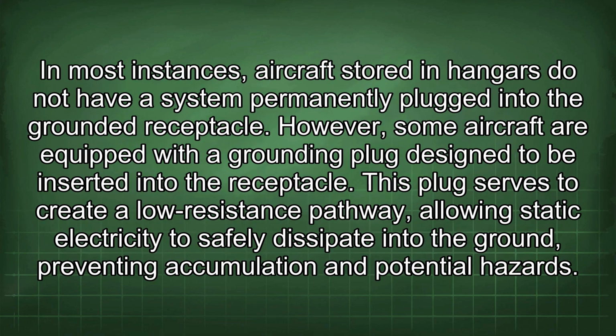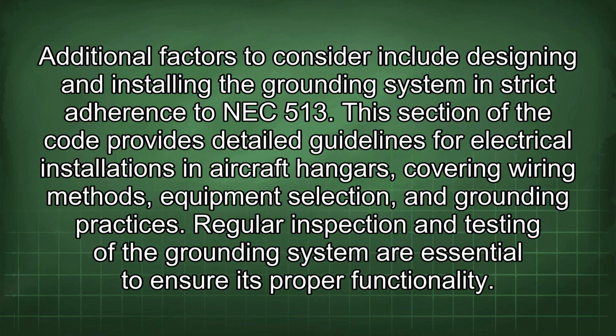In most instances, aircraft stored in hangars do not have a system permanently plugged into the grounded receptacle. However, some aircraft are equipped with a grounding plug designed to be inserted into the receptacle. This plug serves to create a low-resistance pathway, allowing static electricity to safely dissipate into the ground, preventing accumulation and potential hazards. Additional factors to consider include designing and installing the grounding system in strict adherence to NEC 513.